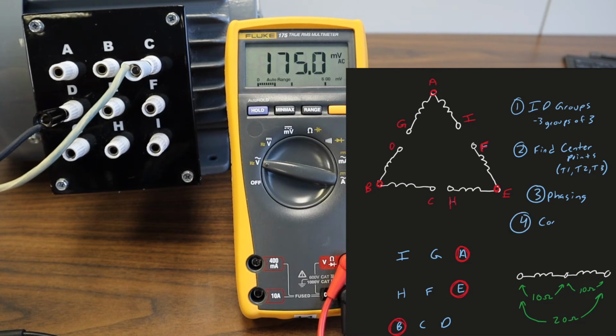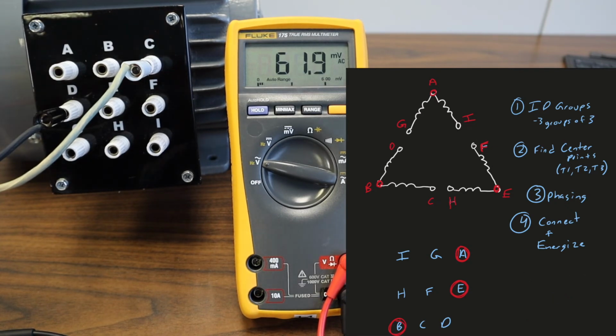Now our fourth step is to connect plus energize. This will depend on whether you're going for a low voltage connection or a high voltage connection. On this motor nameplate, we can see that it's good for 230 volts or 460, meaning 480 or 240 volts. In this situation, we are going to connect this motor for a low voltage connection, which we know is called a parallel connection.